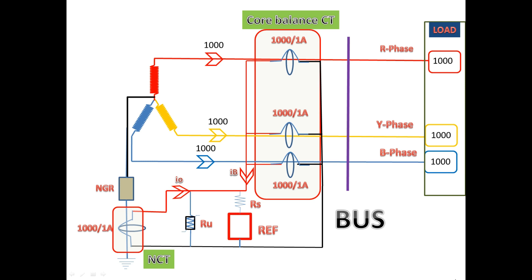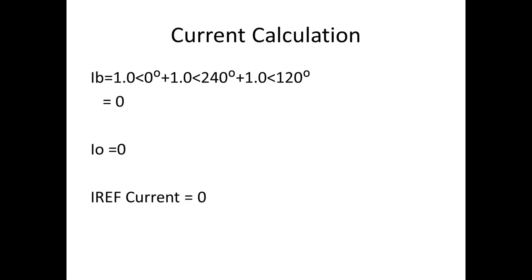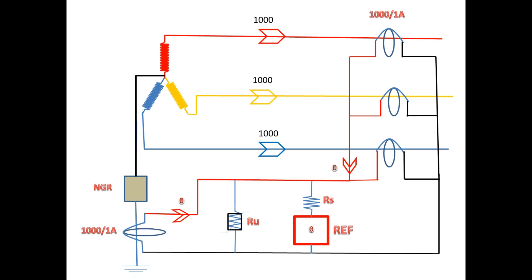Now we consider the load is connected and the load current is 1000 amps in all phases. To find IB, we sum all three phase currents. When we add all three phases, we get zero. Also, there is no current in the neutral CT, so I0 is zero. In this condition, the REF relay will read zero amps and the system will be stable.